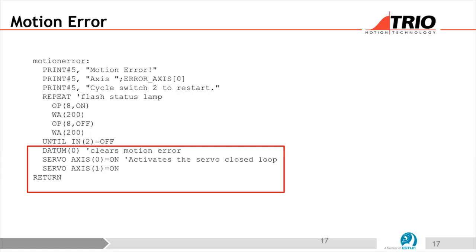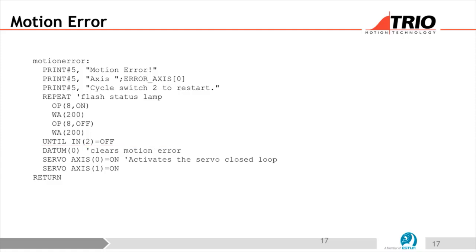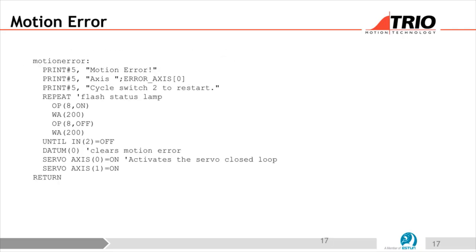Notice we don't turn the watchdog on, we turn the servos on, which just means they're ready for servo processing, but we don't turn the watchdog on at this point. The watchdog is only turned on in the next bit, well, actually the first bit. So you go back to the active state again, which was right at the beginning, to actually do all the enabling. So that's an overview, pictorially, of what is written on the sheets of those program sequences.